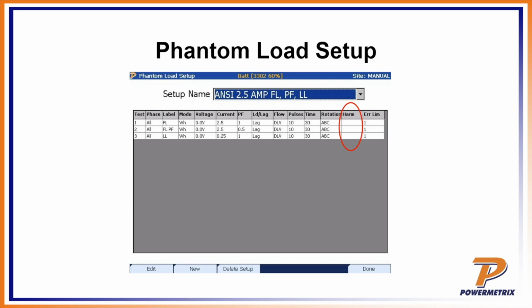The sine is meant to be a true sine wave. It's just sinusoidal. There's no harmonics applied. The phase fired is kind of what Steve was talking about, that shark fin waveform. And the other one is a zero crossing, which is an interesting waveform. I'll kind of show that. So you can actually select that, save that setup, and run this. Now, this new standard that ANSI C12 just came out with is meant for type testing, but you can actually use these same waveforms out in the field to determine how well your meter is doing.